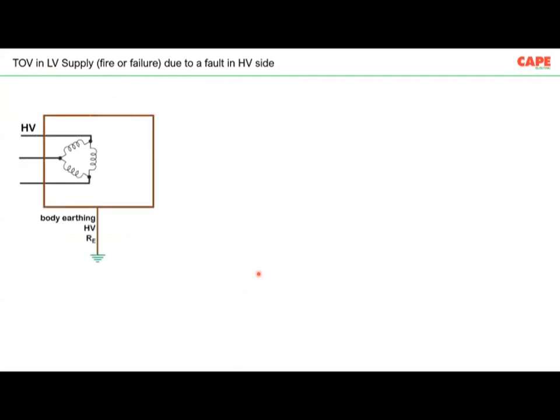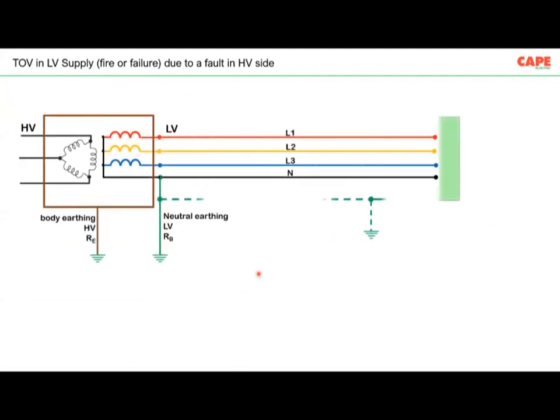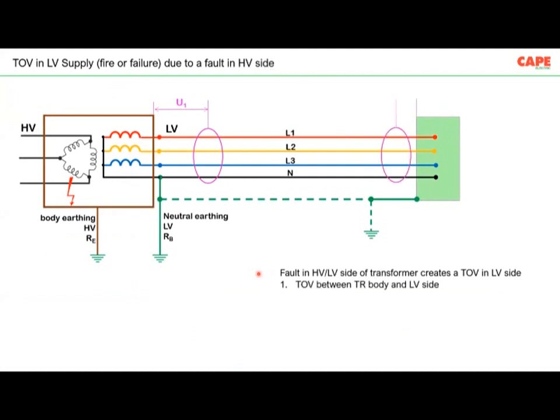Now, another purpose of earthing, which is always creating a hazard without intimation, is a fault in the high voltage system. I'm showing you a transformer, the high voltage winding, the low voltage winding and the low voltage part. A fault in the high voltage system, or HT side of your installation, can create three problems in your building. One is overvoltage at the LT side of the transformer winding. Next one is an overvoltage at your equipment.